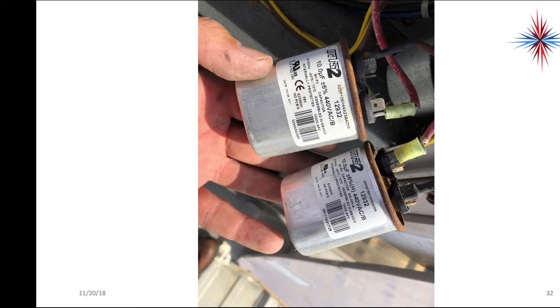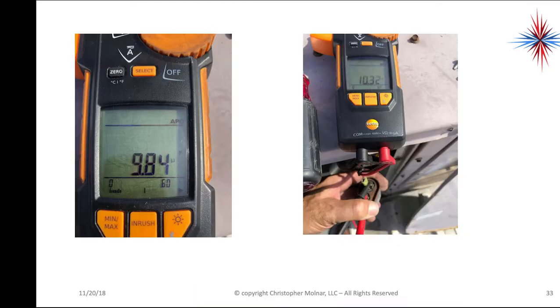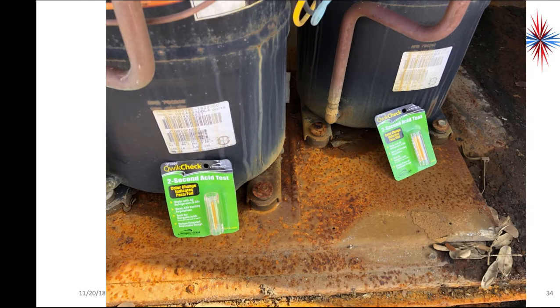Went on to check my capacitors. Okay, the capacitors, there's two of them because there's two condenser fans. They're rated at 10 microfarads. One checked out at 9.84, the other checked out at 10.32. And again, take pictures of it all to make sure it's all valid. Now it's the first time, so that's my electrical with one exception, and the one exception is the indoor fan or the blower. We'll get to that.